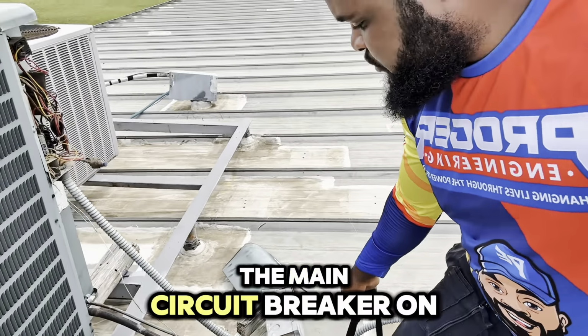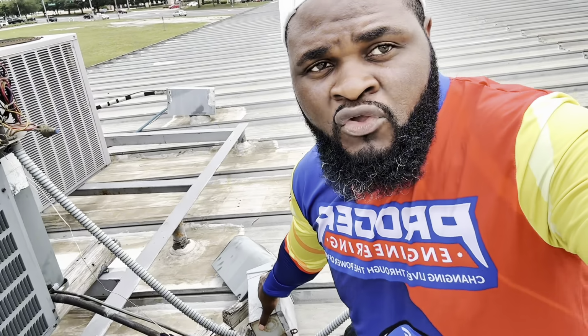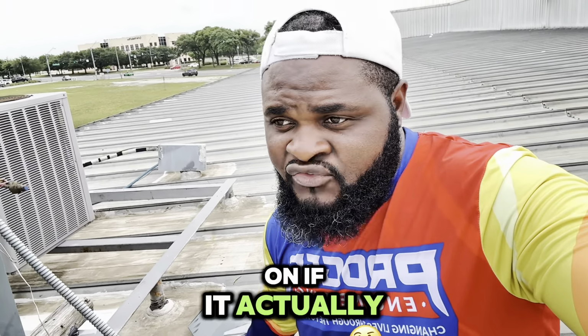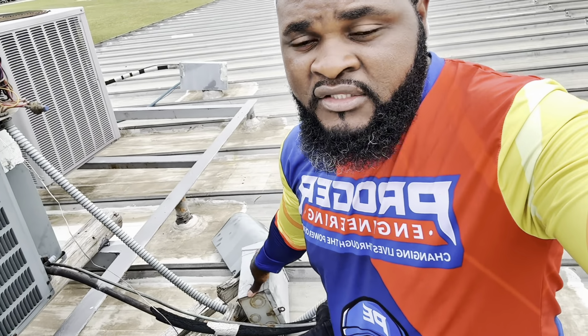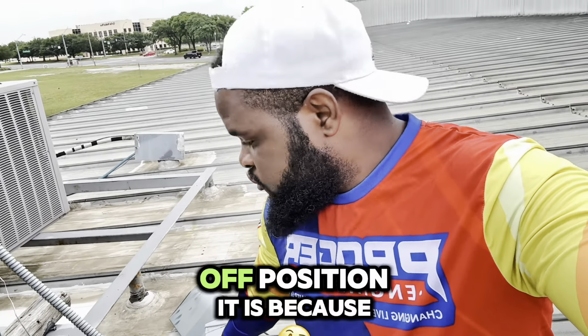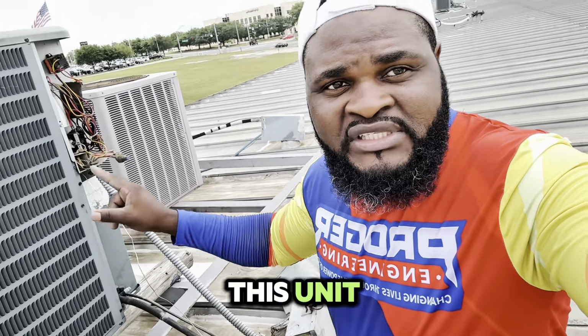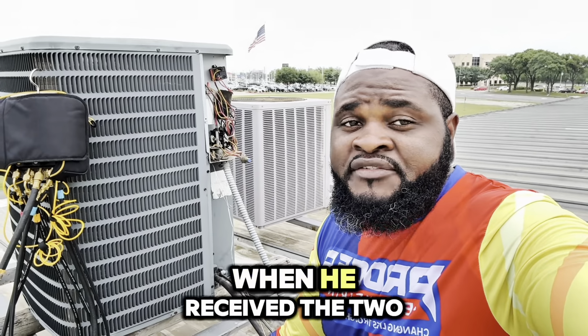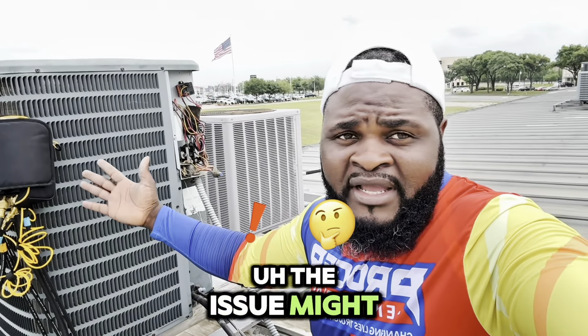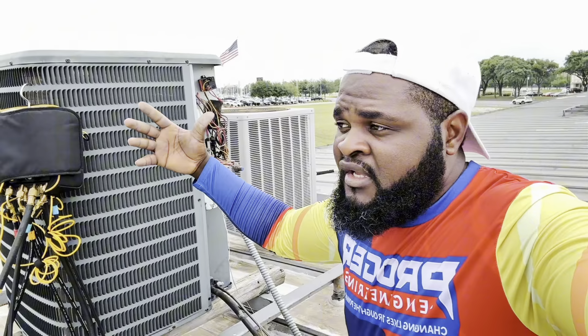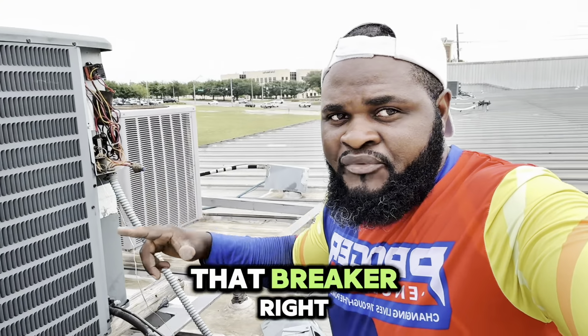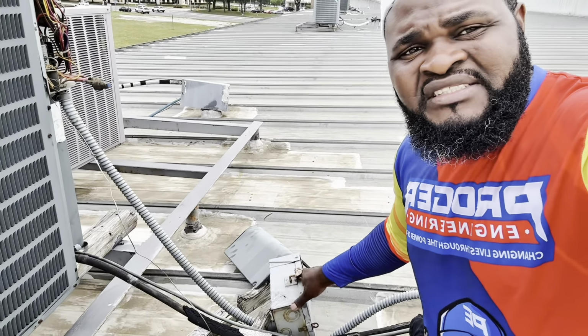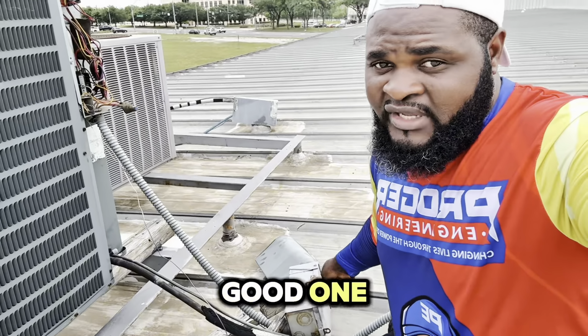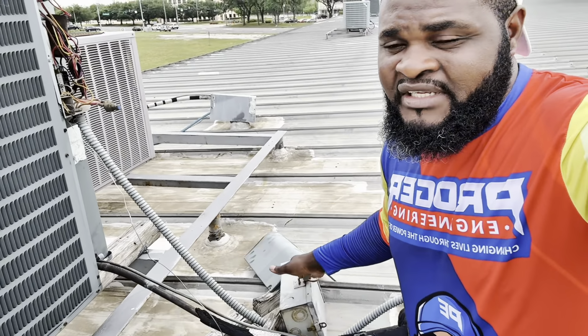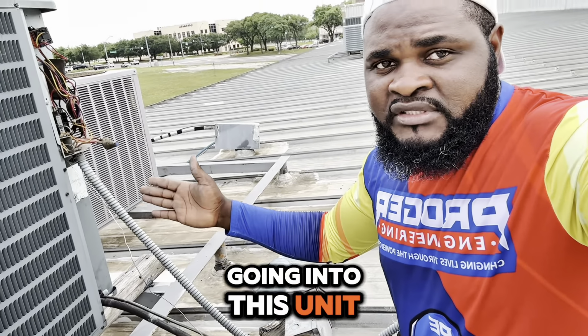And before we turn the main circuit breaker on, we make sure that this disconnect is off. So we will turn it on if it actually trips off and will come up here. The reason why I put this in the off position is because I want to power on this unit and observe how it's going to respond when it receives the 240 volt. The issue might be that the compressor is burnt out, or there's a short circuit somewhere that is actually affecting that breaker, right? Looking at this disconnect is not actually a good one. If there's any short, it's not gonna break or disconnect the power going into this unit. It might only affect the main circuit breaker depending on the amperage drawn.